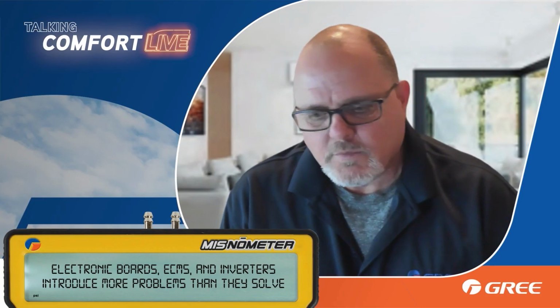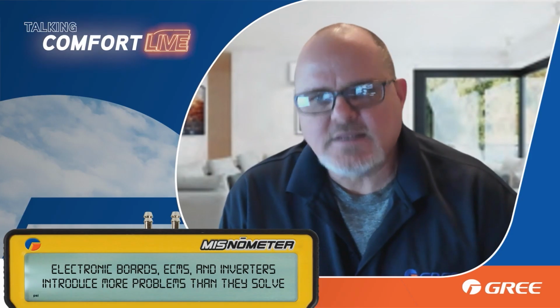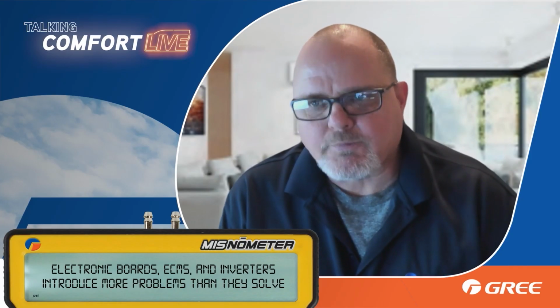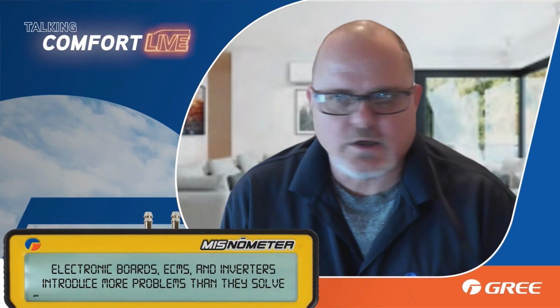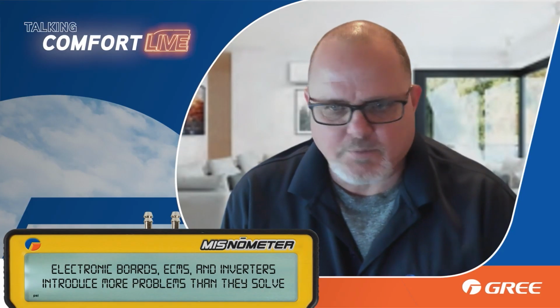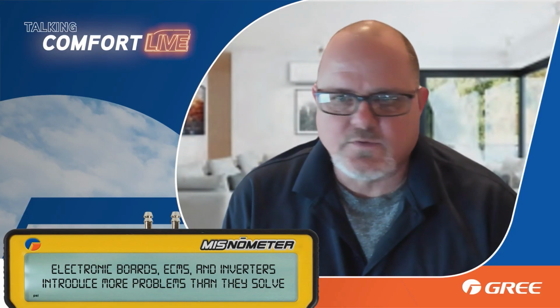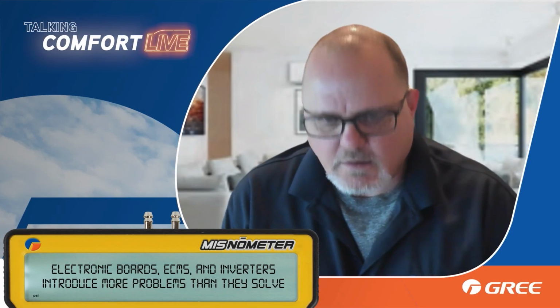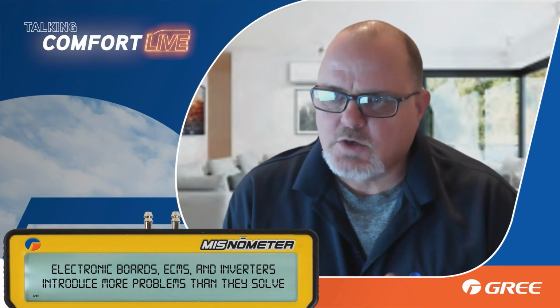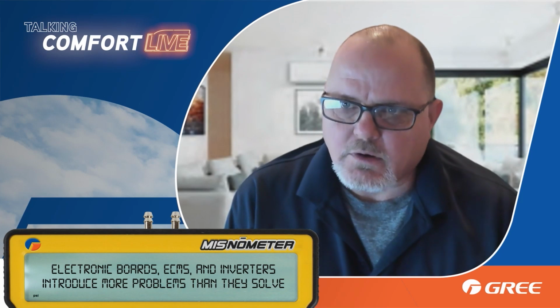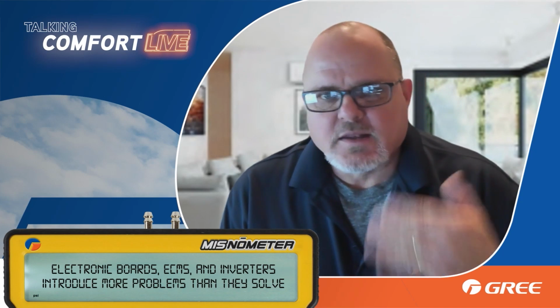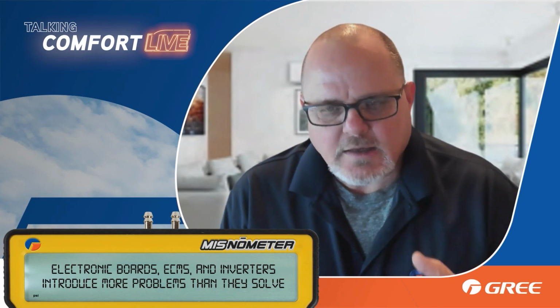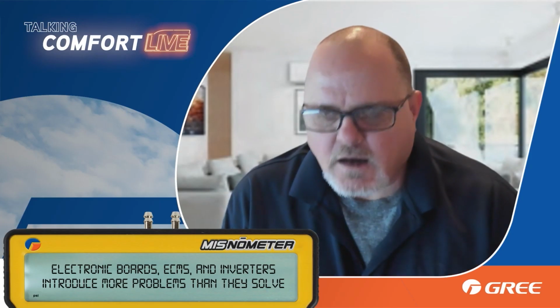Okay, so collectively what that means is you can also measure the amp draw to that compressor just like you would any other compressor. You put an amp probe around the wire and you measure the amp draw to the compressor. You can do that on each lead just like you would on any other 3-phase motor.